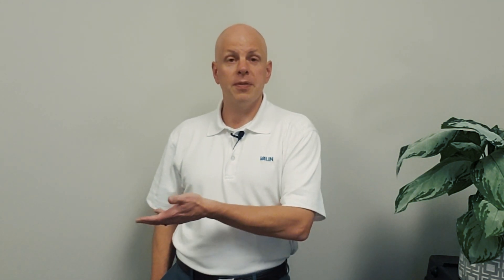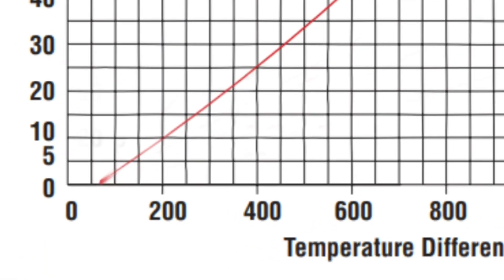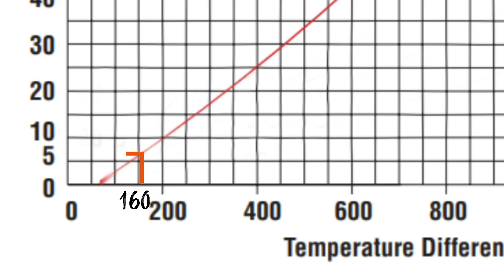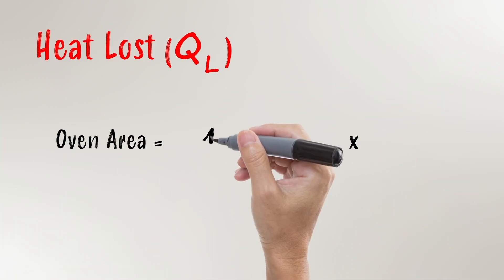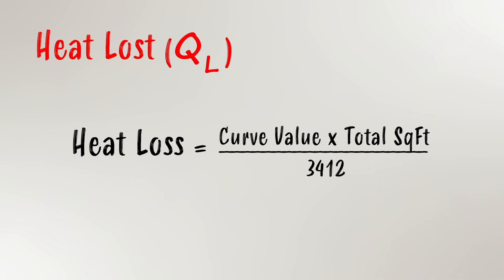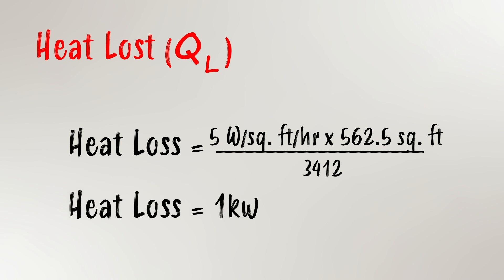Here's the heat loss curve that best fits our application. We can utilize the curve to determine the wattage lost per square foot per hour. In our scenario, due to the two-inch thick insulation and 160-degree difference to the ambient — assuming a 70-degree ambient and 230-degree oven temp — the curve gives us a value of 5 watts per square foot per hour. Next, we calculate the area of the heated container. Because we already have the dimensions, this is fairly easy: length times width times height. Using this formula, we determine the area of the oven is 562.5 square feet. Plugging the values into the heat loss equation, we get a value of about one kilowatt lost to ambient.